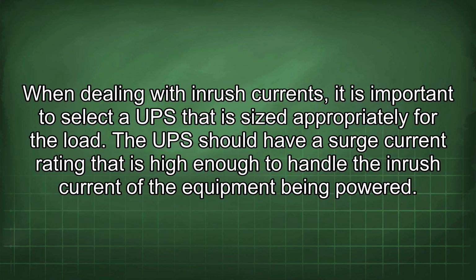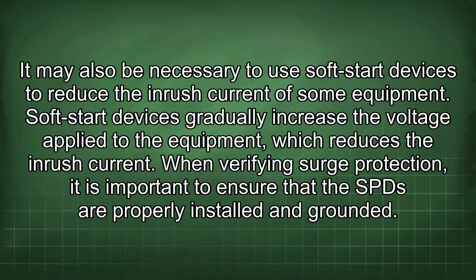When dealing with inrush currents, it is important to select a UPS that is sized appropriately for the load. The UPS should have a surge current rating that is high enough to handle the inrush current of the equipment being powered. It may also be necessary to use soft start devices to reduce the inrush current of some equipment. Soft start devices gradually increase the voltage applied to the equipment, which reduces the inrush current.